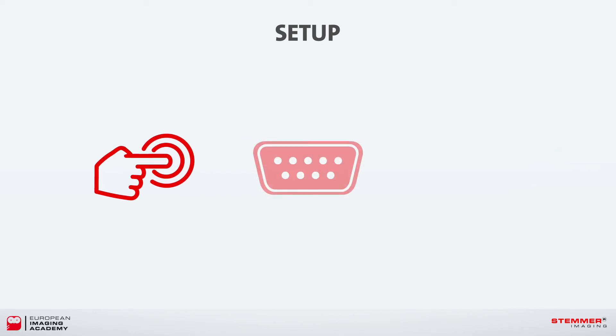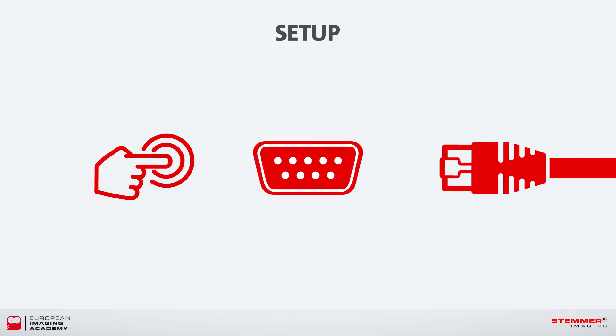You have a few options when configuring lighting controllers. Some have a series of buttons and an LCD screen built directly into them. RS232, TCP/IP or UDP controllers enable control using a simple set of string commands. And some controllers enable you to configure them via a web browser, which accesses its internal web pages. This provides users with a graphical interface for status updates and parameter adjustments.